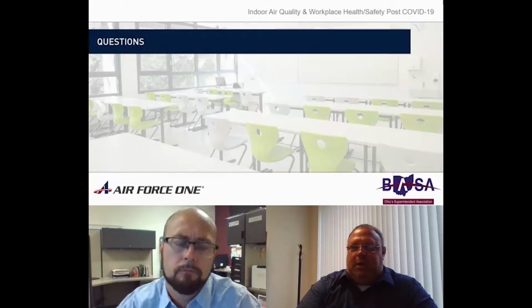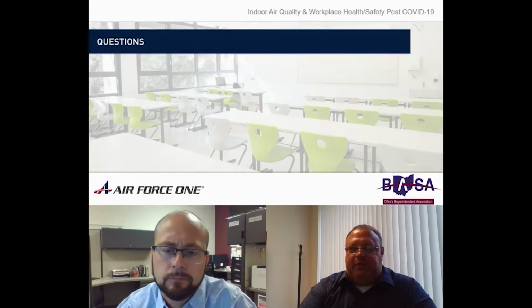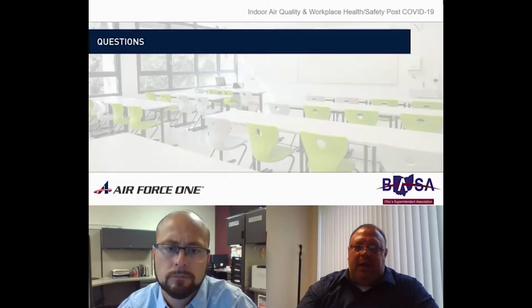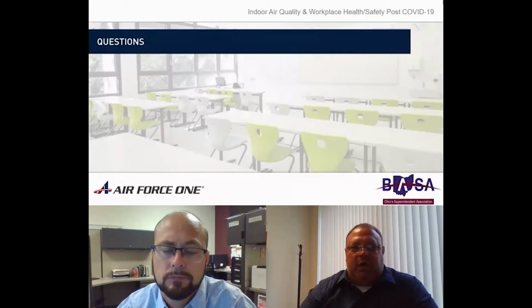One thing I'd like to touch on: some of you are dealing with older buildings where you have natural ventilation, no makeup air, and univents. I know those are still fairly prevalent. In that situation, we have a univent-specific unit. It's a cost that would go on each individual univent and achieve the same thing, albeit sometimes at a little higher cost, because even though the equipment price is lower on a smaller device, you end up with more labor and it scales up due to the quantity.